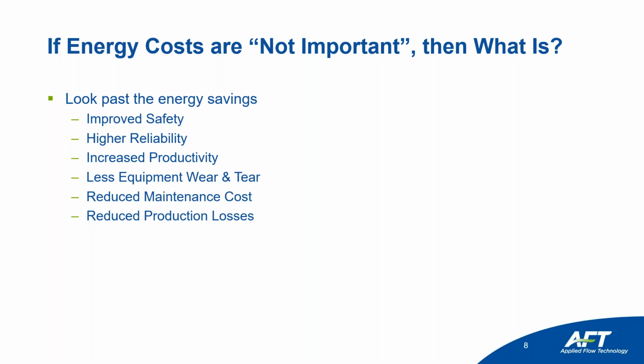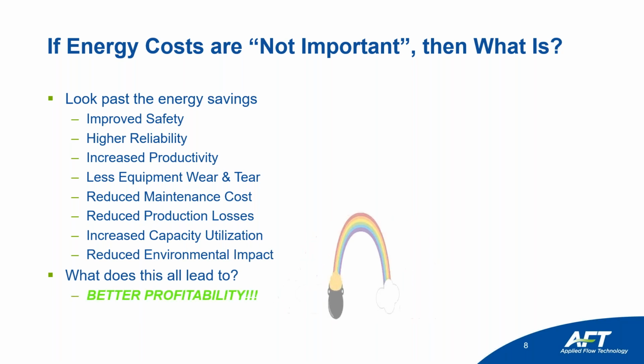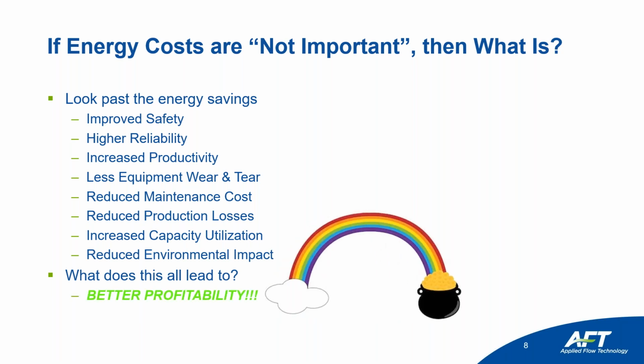That's a key issue. If you're running your system at way too high of pressures, maybe you've got leaks happening throughout your network, and that's production losses. You can increase the capacity utilization you already have. And so, as I mentioned, a lot of these systems were way oversized. Well, if you did a good flow analysis to learn how to operate the system more efficiently, then you'd be able to utilize what your system could already do without maybe having to make any system modifications. Reduced environmental impact. What does this all lead to? Better profitability. And so it's all about the money.